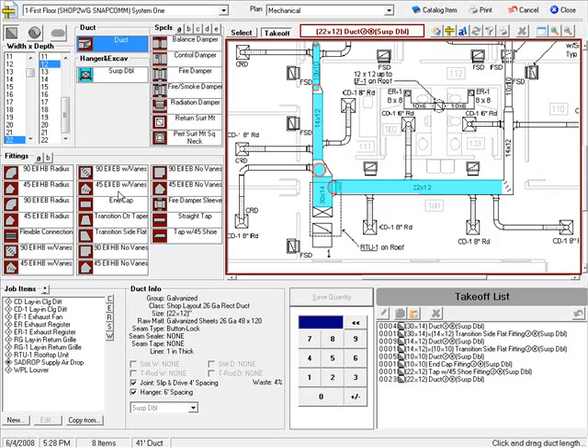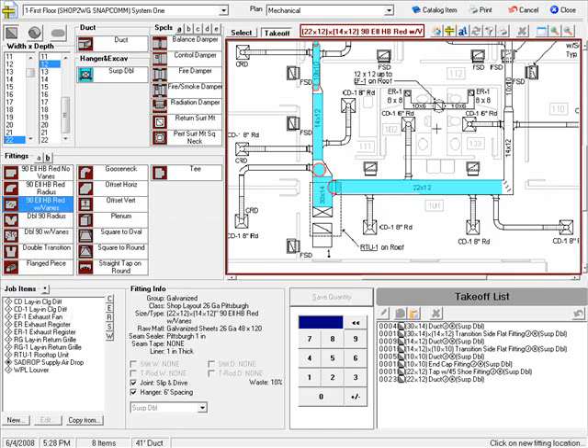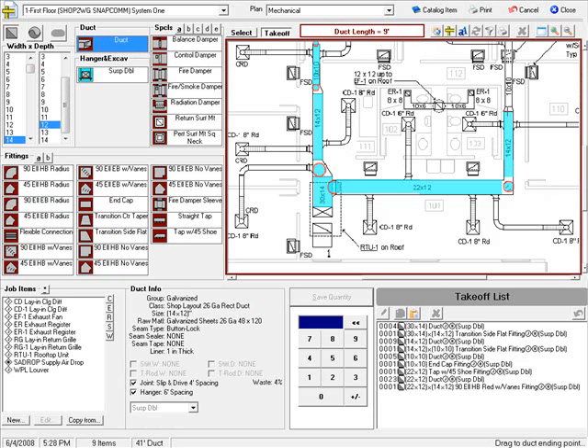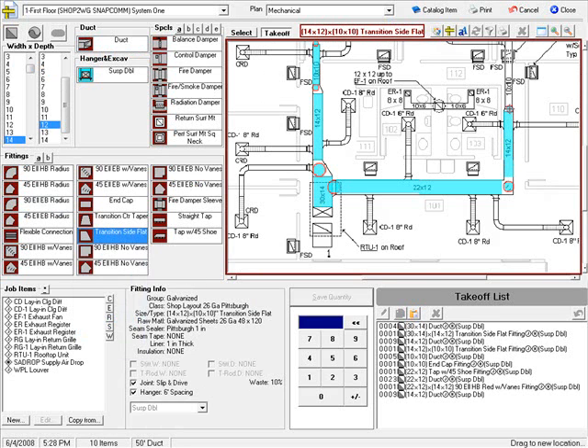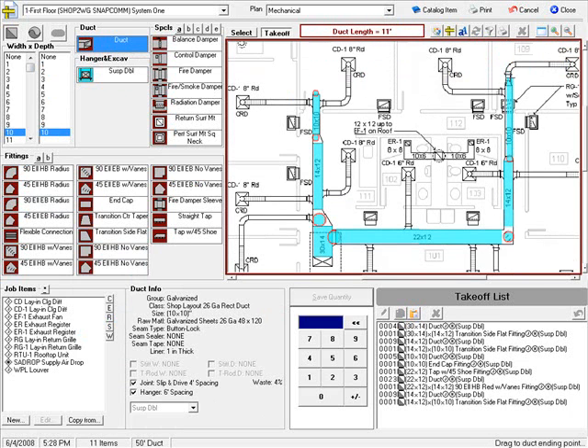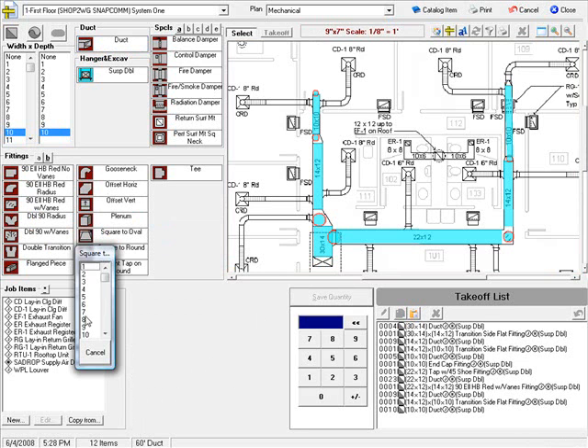And a 22 by 12 to 14 by 12 hard bend with vanes. My reducing elbows aren't on my front page — my A list. I go to my B list, and I have a 90 degree hard bend with vanes going to 14 by 12, then 14 by 12 duct, a 10 by 10 transition, and 10 by 10 duct. Again, a 10 by 10 to 8 inch square to round — not on my A list of fittings, it's back in the B list. Square to round to 8 inches.